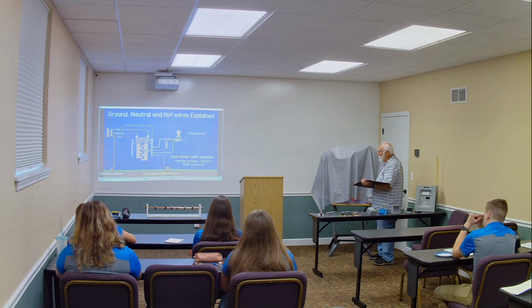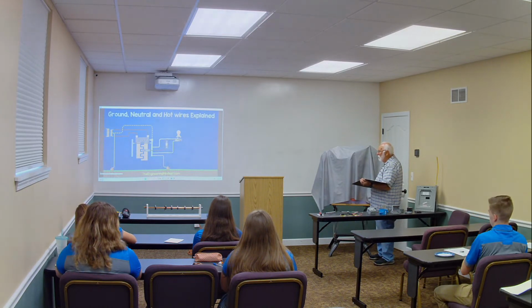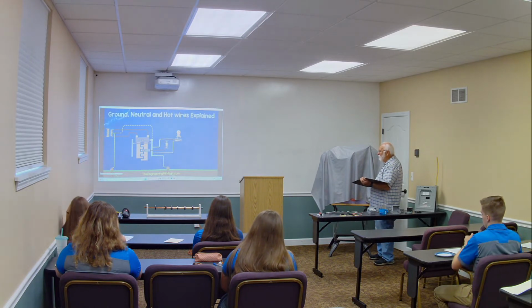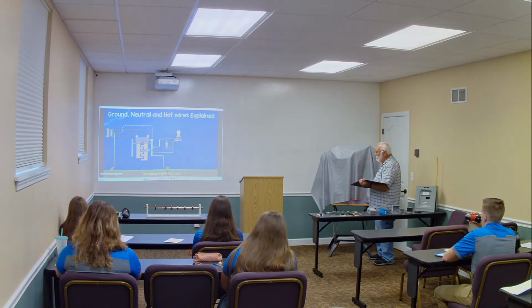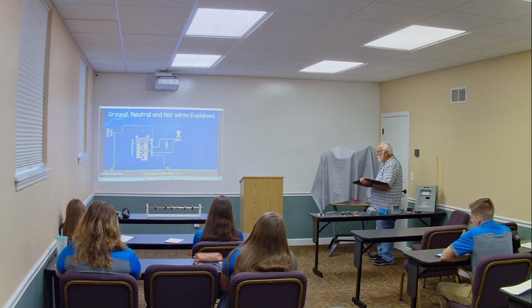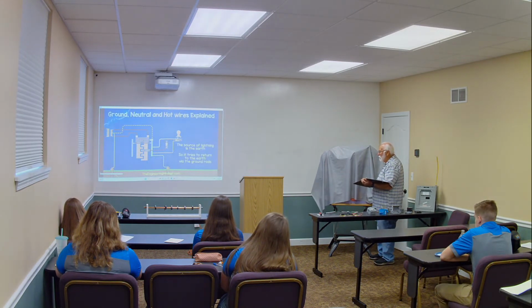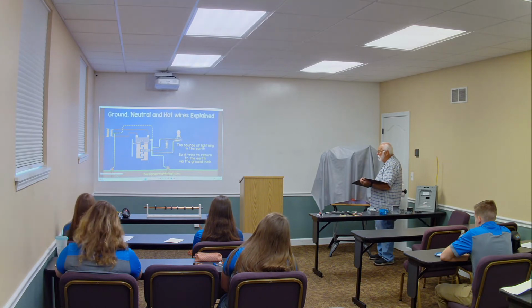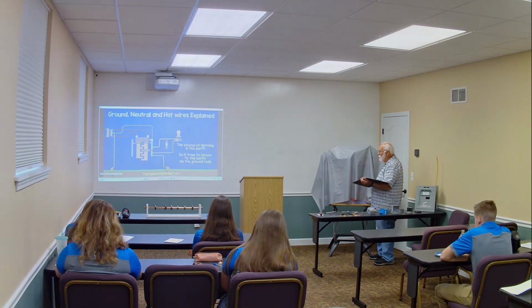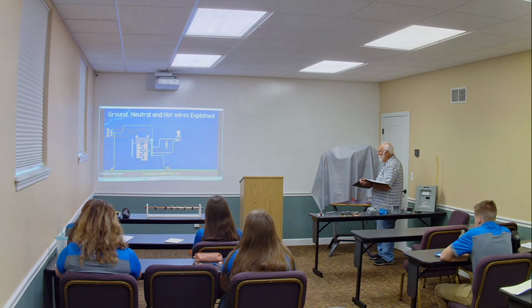When it comes to lightning, the source of lightning is essentially the earth, so lightning is always trying to get back to its source. If lightning strikes the utility cables, it flows along the wires to reach the ground rods of both the transformer and your main panel, trying to get back into the earth. If it wasn't for this, it would blow all our circuits and cause house fires.